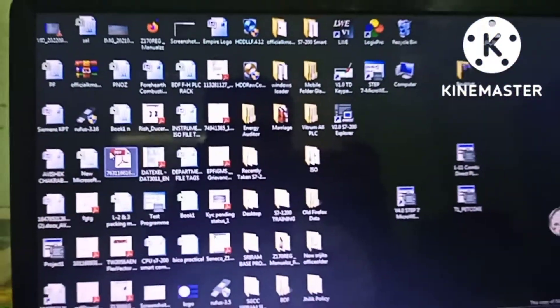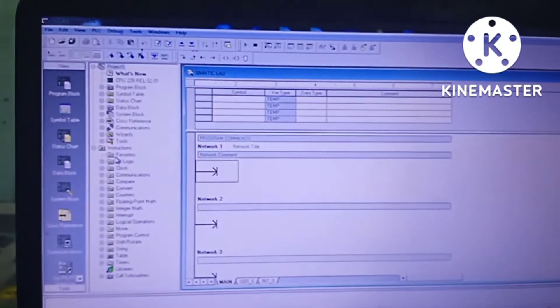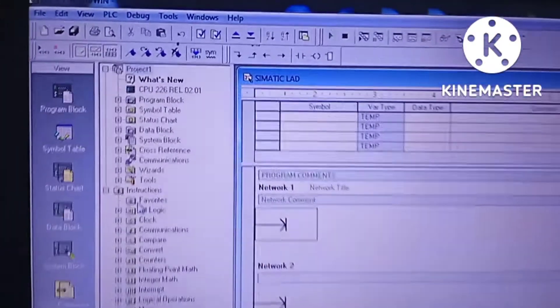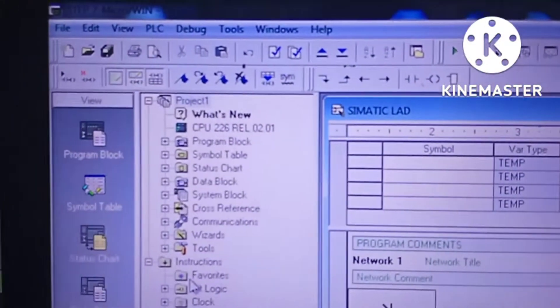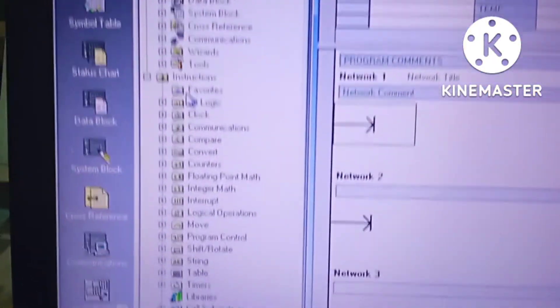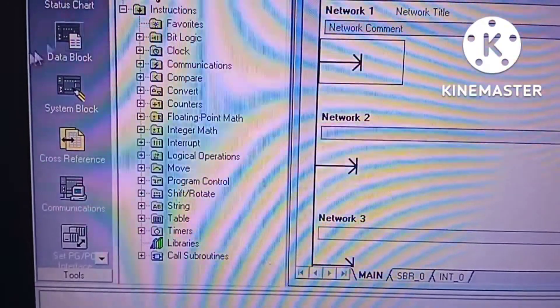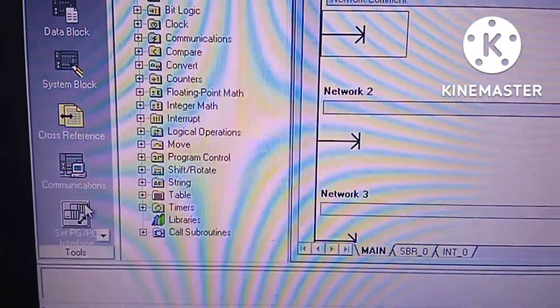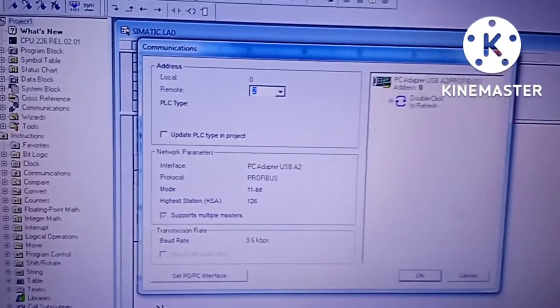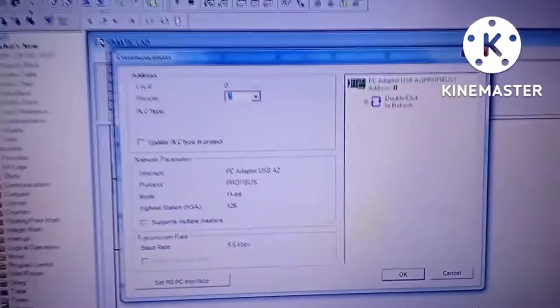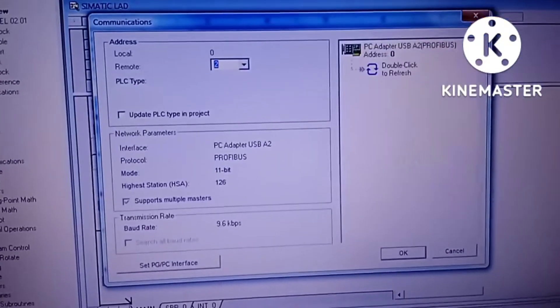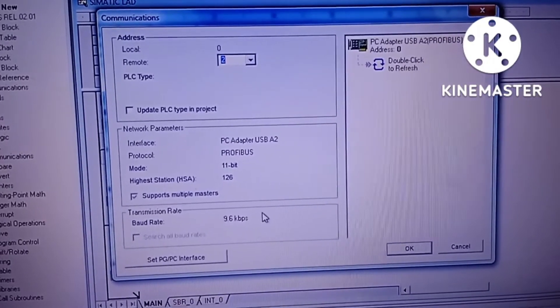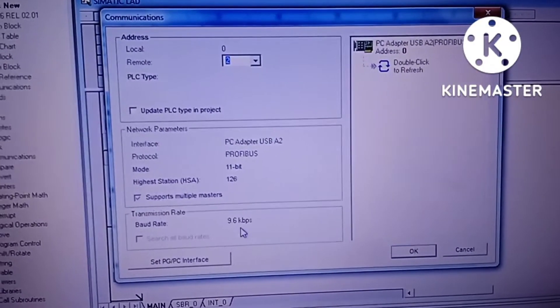The software opens. First of all, we have to establish the communication between the PC and the PLC. To establish the communication, we have to go to communications header. Here, look carefully. Network parameter is PC adapter USB A2, protocol is PROFIBUS, and baud rate is 9.6 kbps.